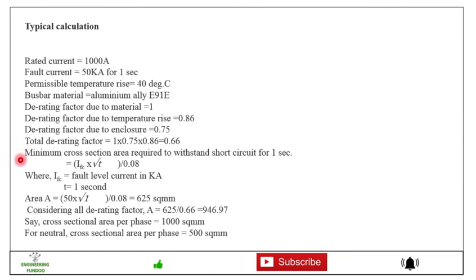In that case, minimum cross section area required to withstand short circuit for one second will be equal to IFC into under root of T divided by 0.08, where IFC is the fault level current in kilo A and T is the one second time. Area A is calculated, here you can see it will be 625 square mm. Considering all derating factor, now if we consider derating factor for temperature rise in enclosure condition, 625 divided by 0.66 will come 946 square mm. So cross section area per phase we need to take 1000 square mm, that is the next higher size, rounded figure, standard size available.